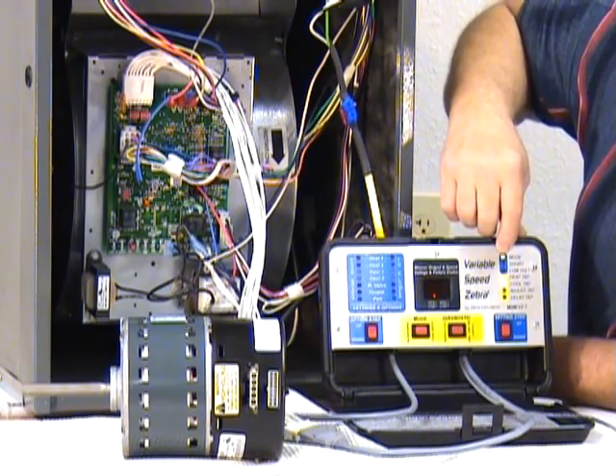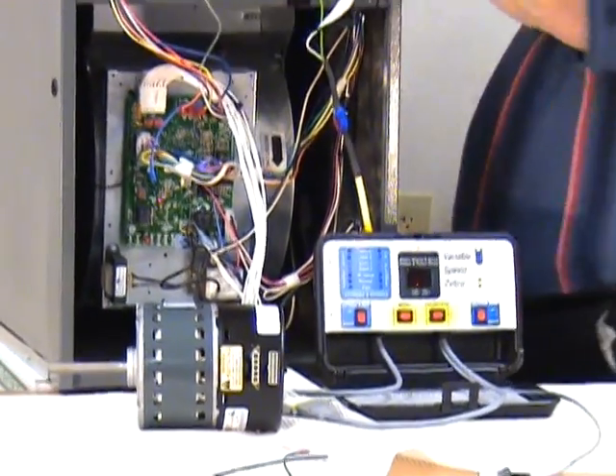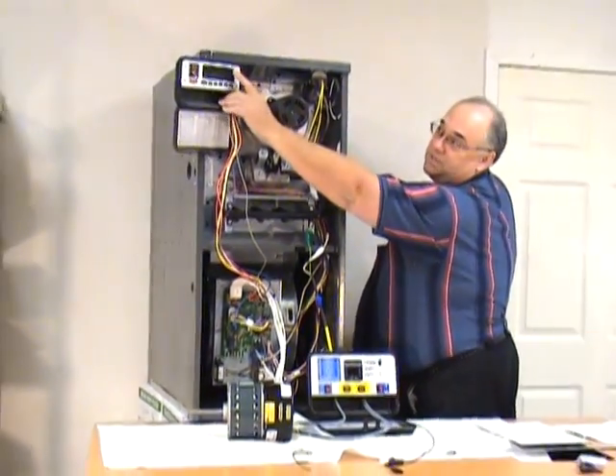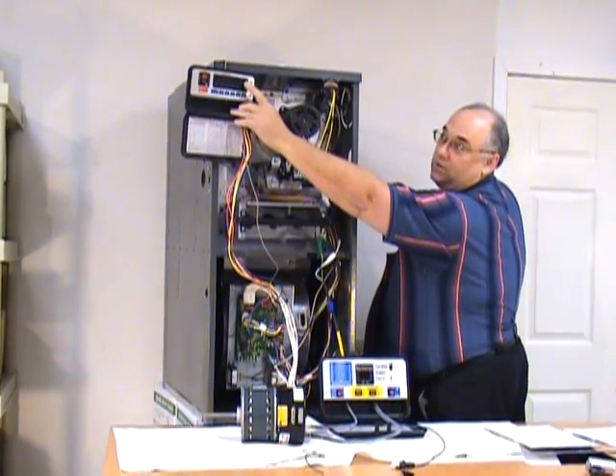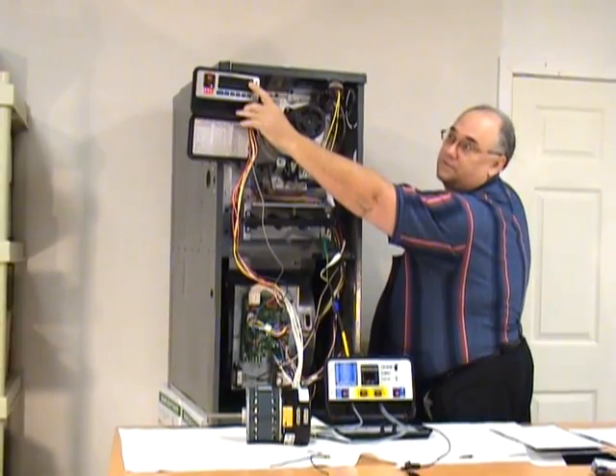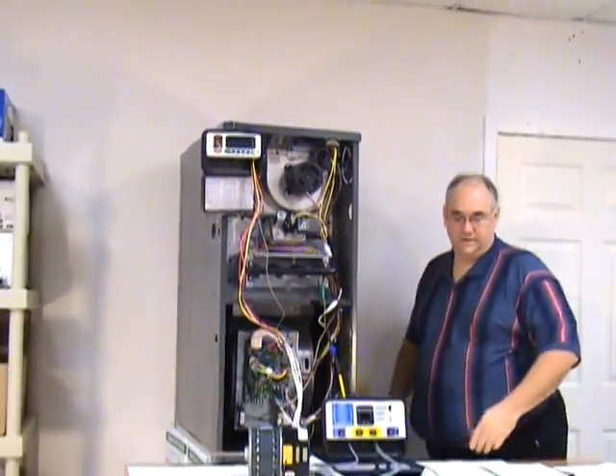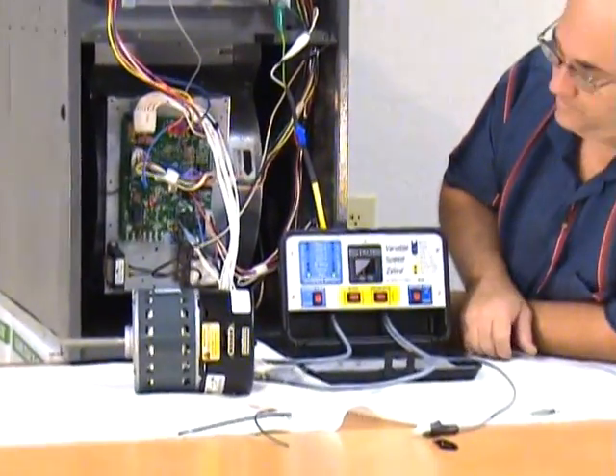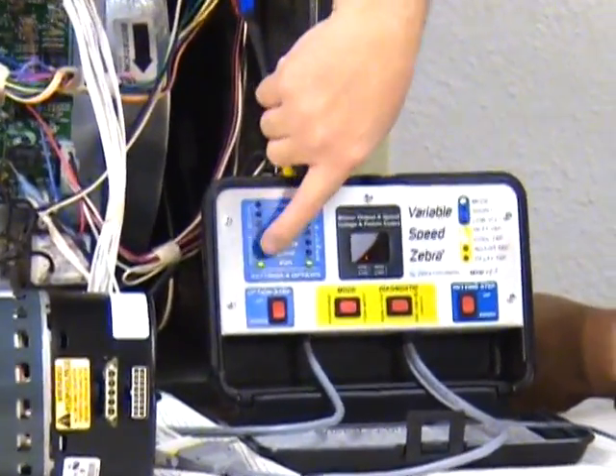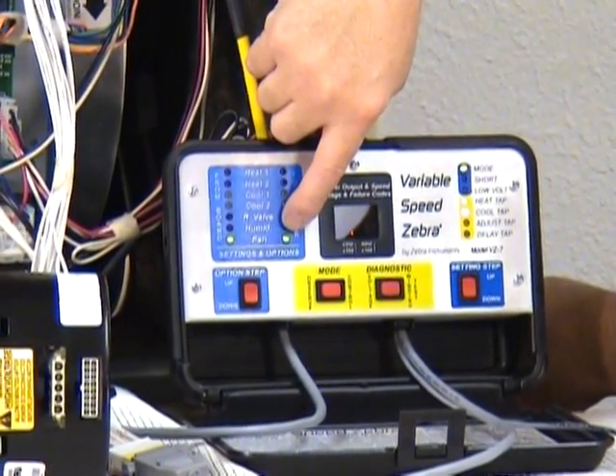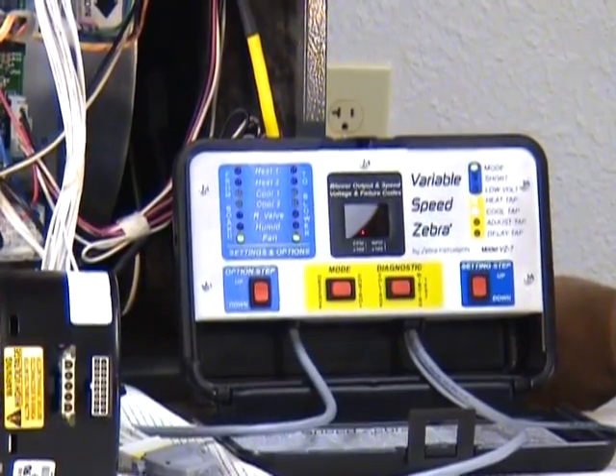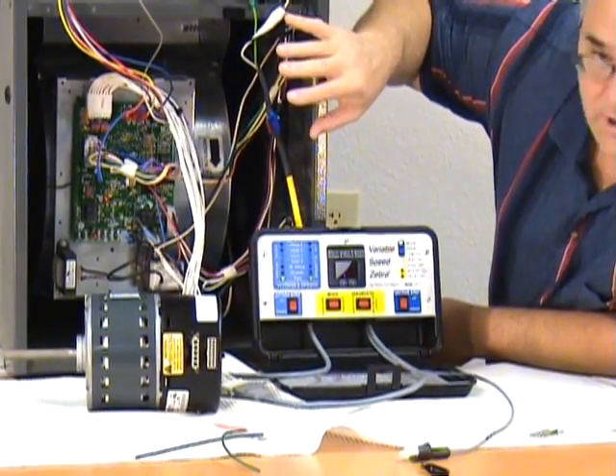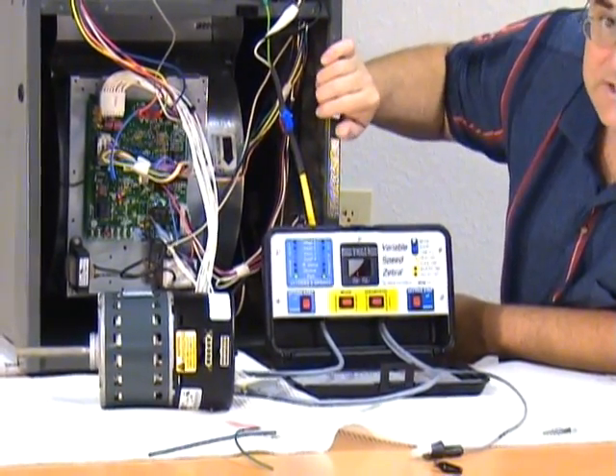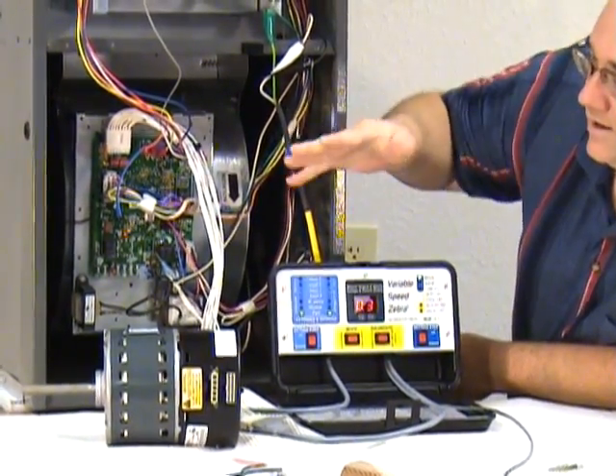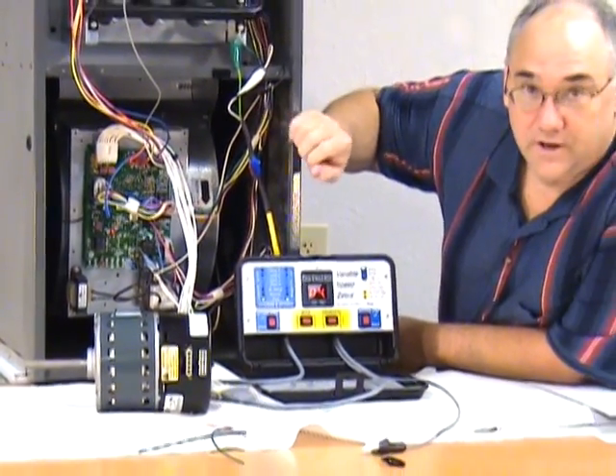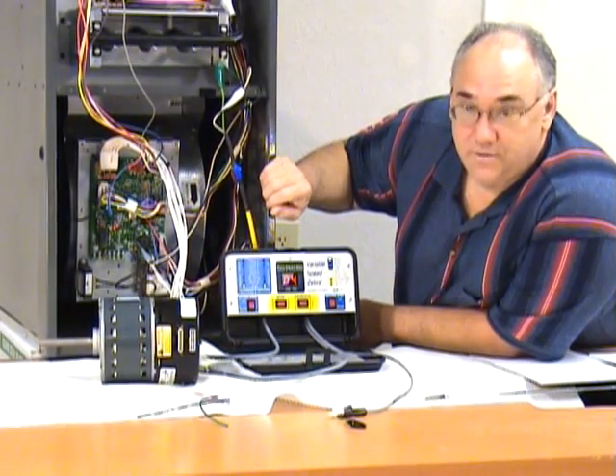I'm going to use, pan out for just a second, Lisa. We're going to use our ZebraStat to replace the thermostat, and we're going to turn the fan line on this furnace. Okay, let's go back and focus down here. After a few moments, that circuit board sends a signal down the fan lines to the motor, and you might even see the circuit board shaking as it's rocking that motor back and forth, trying to determine which speed, which direction to start at. By the way, that's a characteristic of those motors, that they hunt back and forth a little bit when they first start up. There's nothing abnormal about that. It's not a cause to replace a motor.